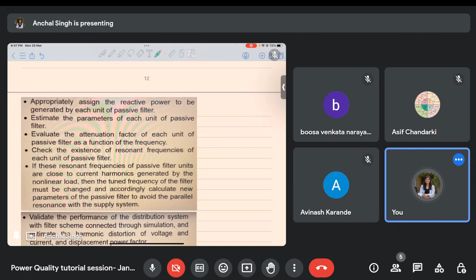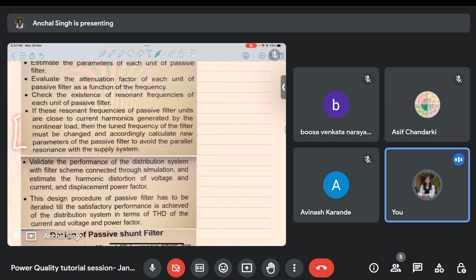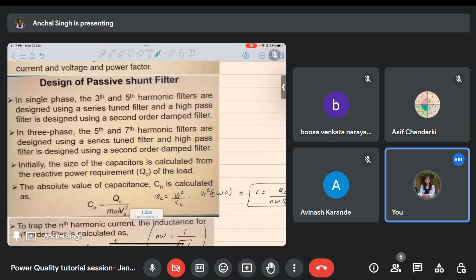Now I am validating that design for the problem of resonance. I check what is the resonance frequency of my system. And if my system has a harmonic which is coinciding with the resonant frequency, that I will check. And if that is a problem, then I'll keep on repeating the steps again and again. Okay.